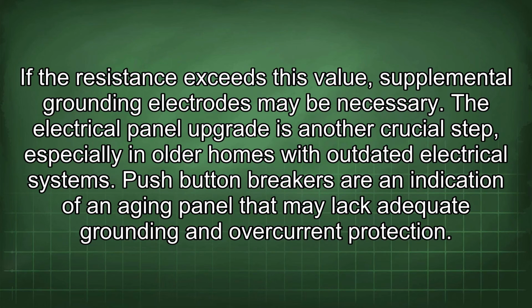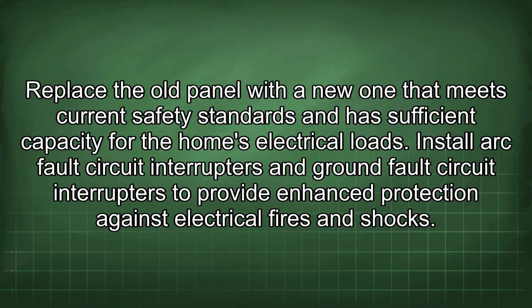The electrical panel upgrade is another crucial step, especially in older homes with outdated electrical systems. Push-button breakers are an indication of an aging panel that may lack adequate grounding and overcurrent protection. Replace the old panel with a new one that meets current safety standards and has sufficient capacity for the home's electrical loads.